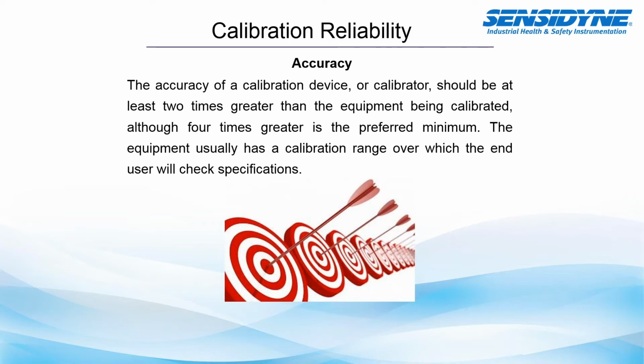Now, the accuracy of the calibration device or calibrator should be at least 2 times greater than the equipment being calibrated. Although 4 times is the preferred minimum, 2 times is an acceptable limit. The equipment usually has a calibration range over which the end user will check the specifications. It's important to make sure that you match up and align the right size calibrator for the right size airflow source. In other words, if I'm sampling or trying to prepare a low flow sampling pump, I'd want to make sure that I was using a calibrator that had a low flow specified range that I could accurately measure the airflow and calibrate my airflow source.